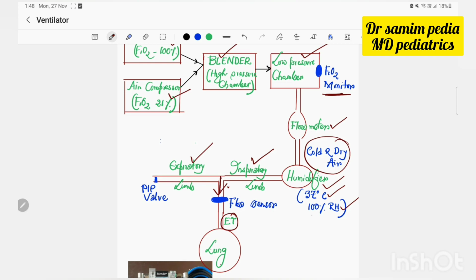Between the Y connector and the endotracheal tube there is a flow sensor which senses how much air goes into the lung, that is minute ventilation or tidal volume. Tidal volume is how much air goes into the lung per breath, and minute ventilation is how much air goes into the lung per minute. In the expiratory limb there is a valve. This is called the PIP valve. This valve maintains the PIP pressure during inspiration and maintains the PEEP pressure during expiration.